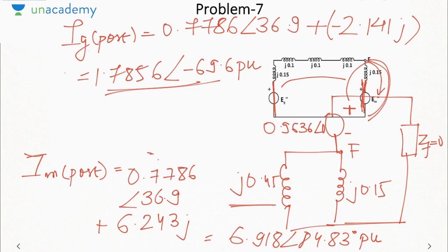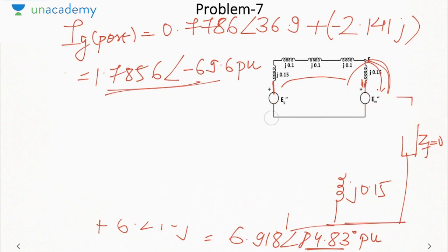Okay. Now if you see here, the voltage is actually angle 0, but the motor current is coming angle 84.83. That is, the motor current is leading the voltage. Now as I told you, the fault power factor is always lagging. Then how come the motor current is leading the voltage? Here also there is a fault, so the fault current must have been lagging. The problem is that the motor is delivering the current and I am assuming the current is going into the motor. So actually the assumed direction and the actual direction of the motor current are opposite. And if you draw the opposite of a lagging phasor, what you will get is a leading phasor.